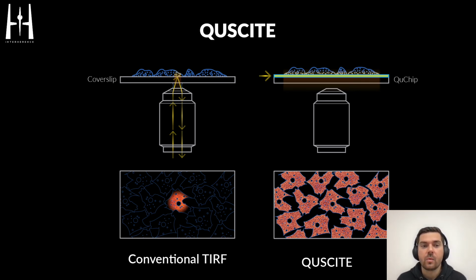So what we do is, instead of sending the beam into an objective and then exciting locally a small area of the sample, we exploit a thin film waveguide that is sitting on top of a glass chip that supports a guided mode. And that guided mode has a strong evanescent field tail entering into the sample volume. So when there's a cell culture sitting on top of the waveguide and there's an optical mode launched into that thin film, the cell culture feels the evanescent field of the waveguide and can be excited everywhere where the waveguide is. And now you in principle decouple the excitation completely from the detection.